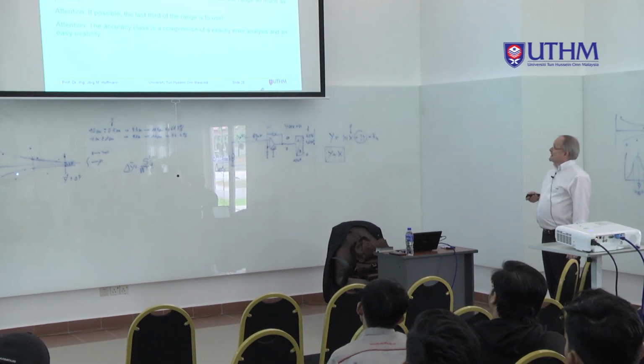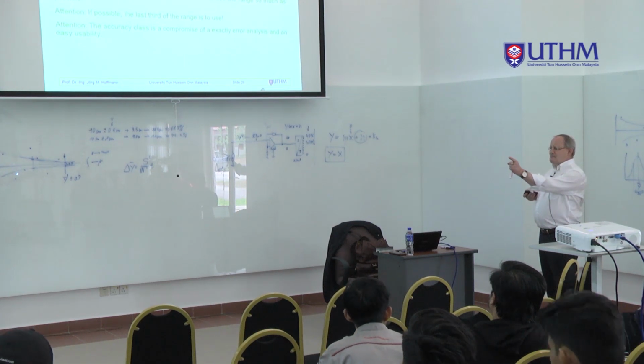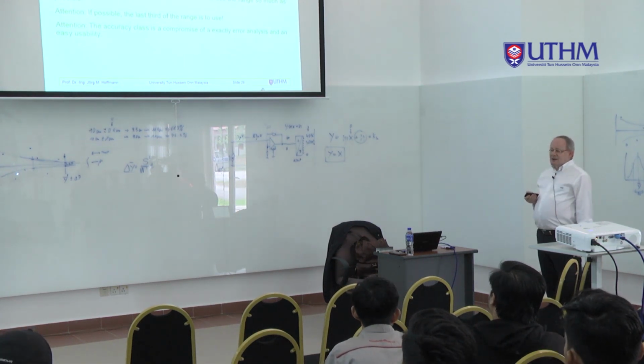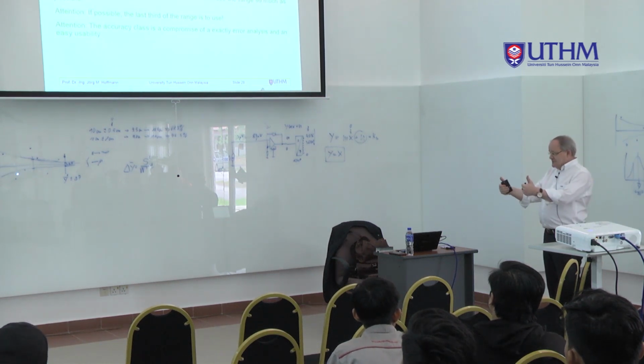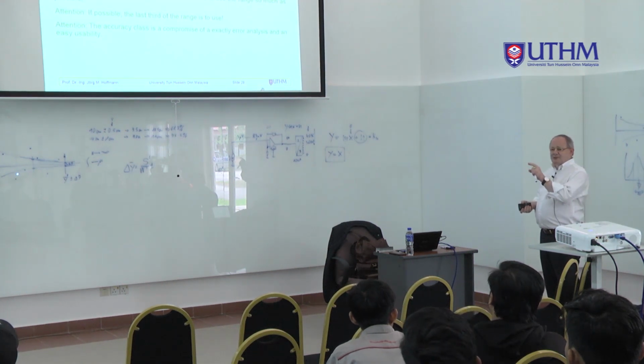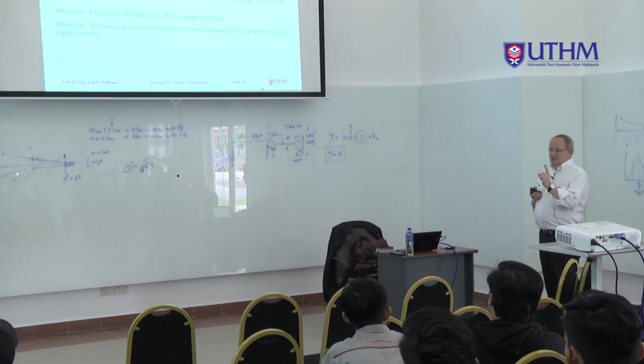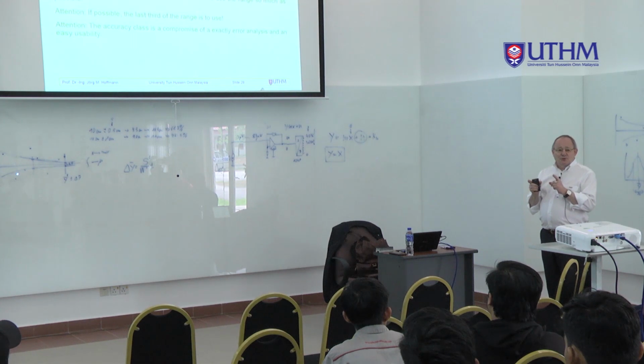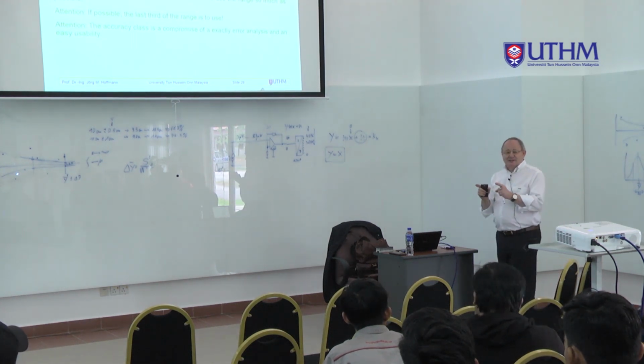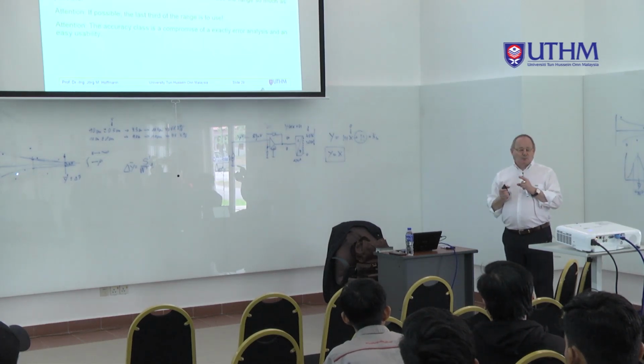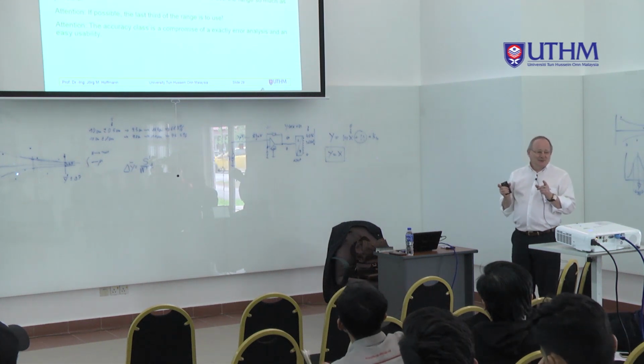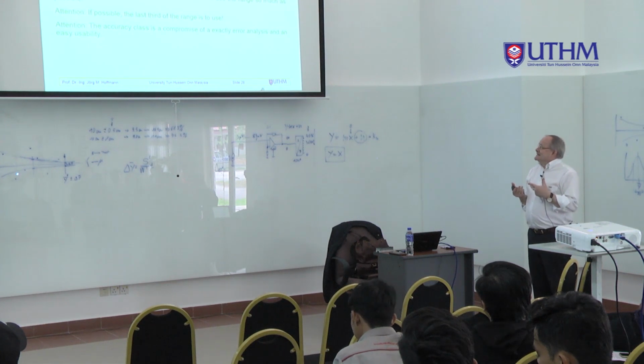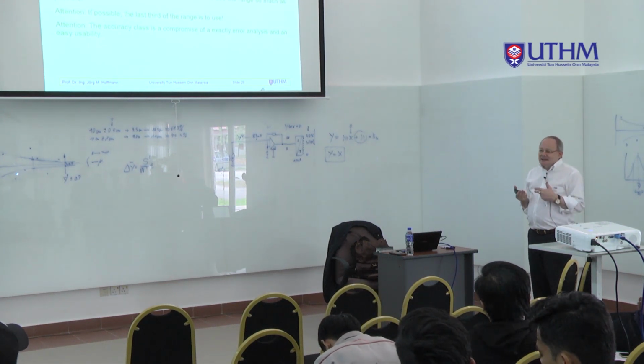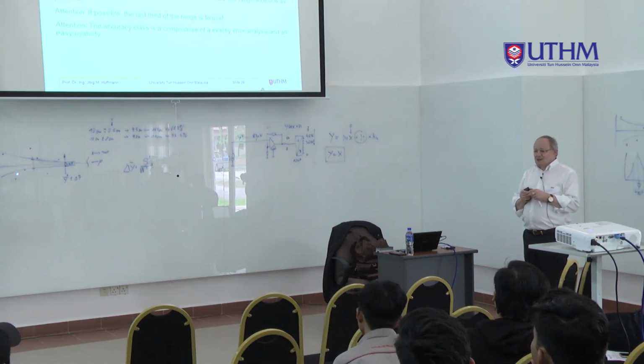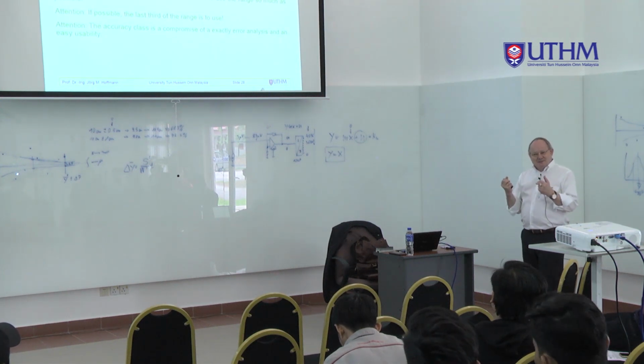What do they do? They say, I measure many, many times, look for the biggest error, the biggest single error. And then they say, I have an error, let me say, from the true value, the difference from the true value, 1.2%. So that I have measured already. And now, to be sure that the customer never measures a bigger error, they put a little bit on top. And that is not a scientific method. That depends on what the company likes, whether they should be absolutely sure, or whether they think a little bit of advertising is also good. Then they reduce it a little bit.